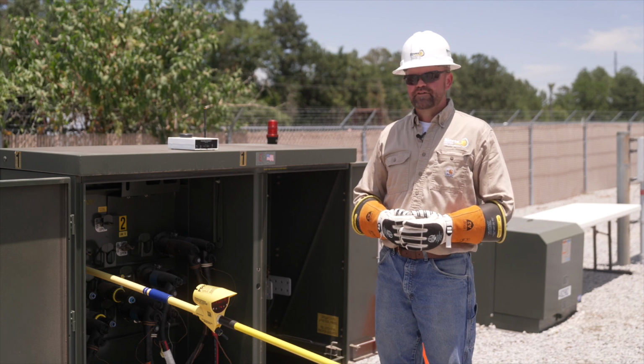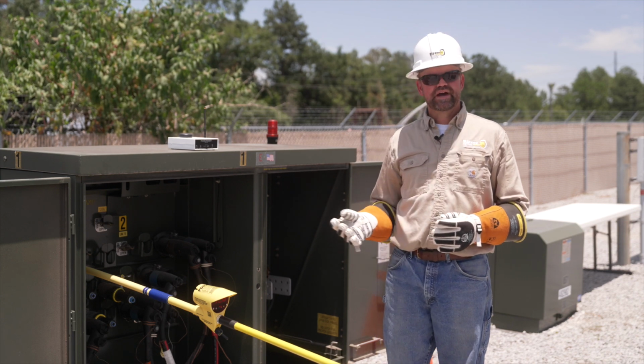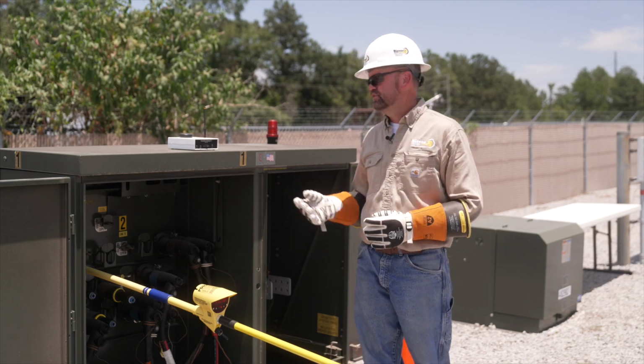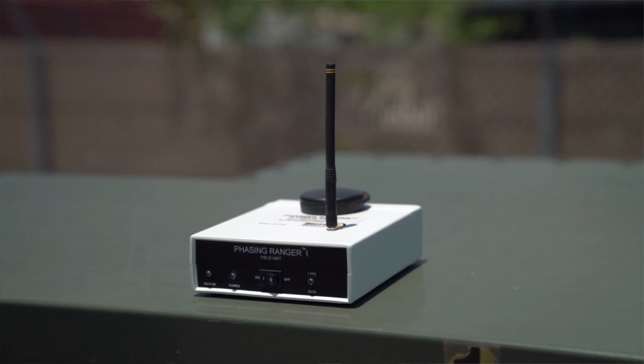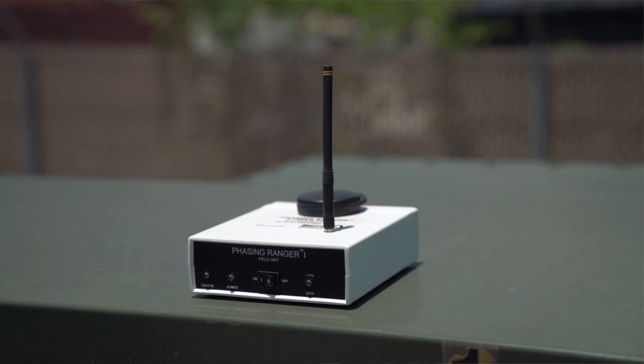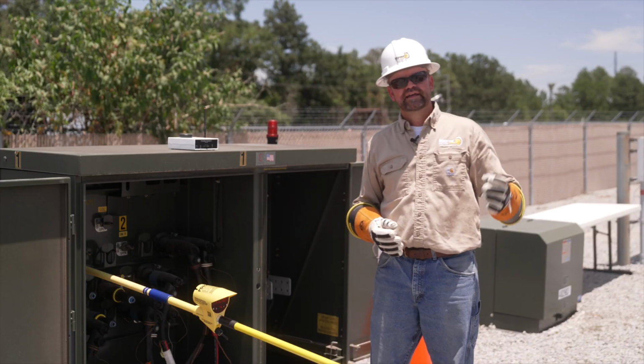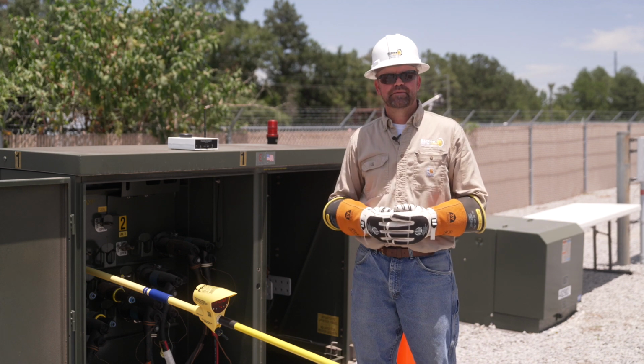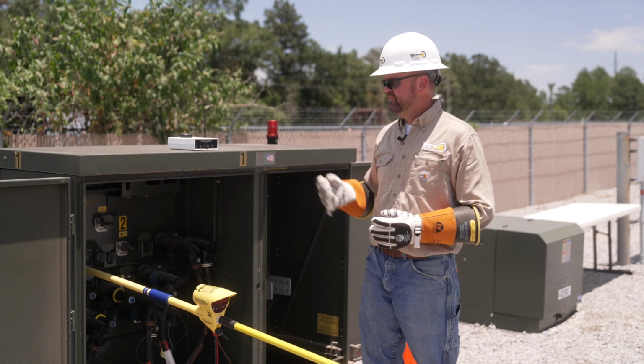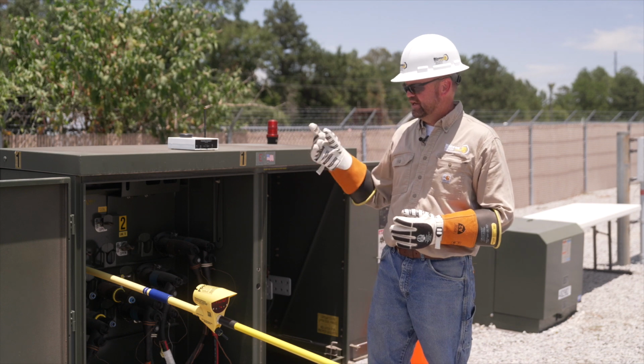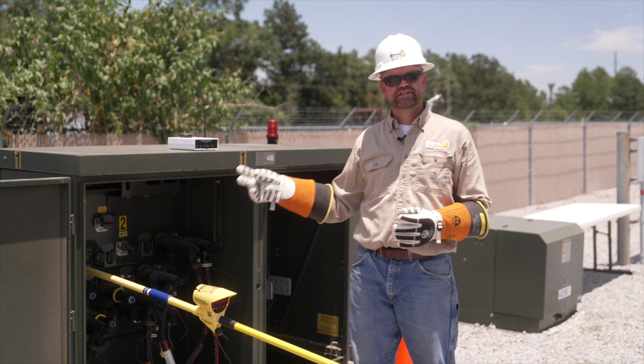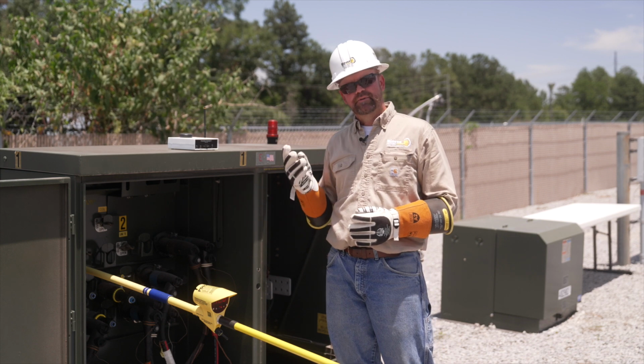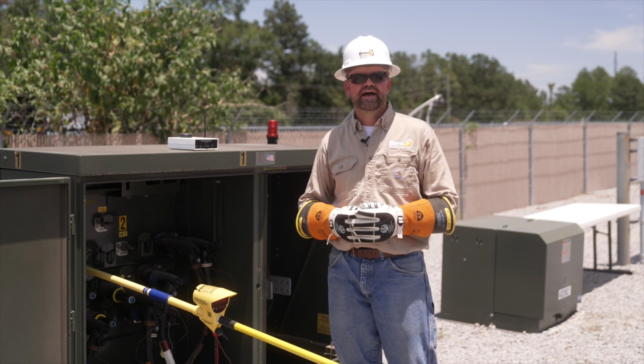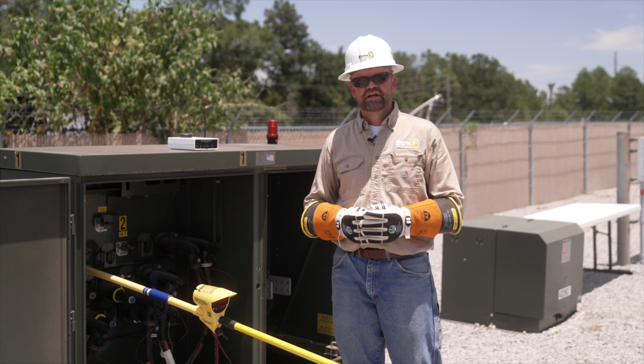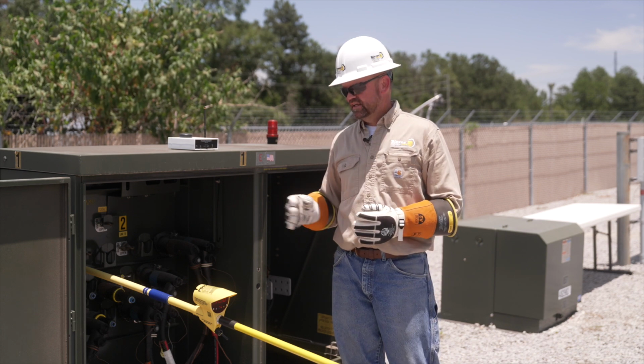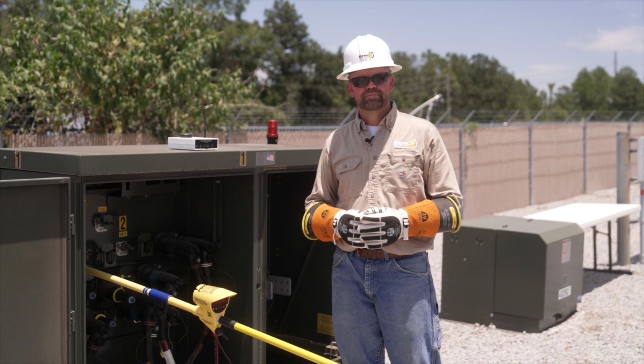If you want to determine what phase is what, so actually phase ID, we encourage you to look at our phasing ranger. In other words, this white box right here, it would connect to a base station, it would replace my reference probe, and in that case I would actually do 4 things simultaneous. So the addition would be phase ID. So again, I would take my nominal voltage reading, I would be phase sequencing, I would phase, and I would actually phase ID, all in real time. So again, that's a very unique feature. I believe we're the only manufacturer that does that. And again, you can do it all in one move using this one probe.